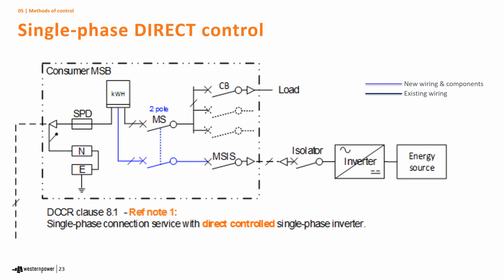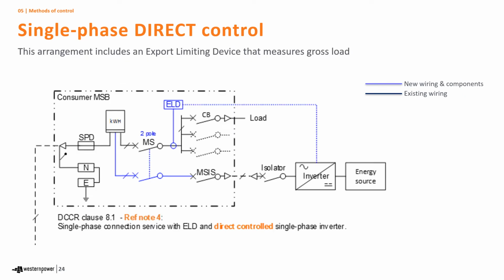Let's move on to the next example. In this example, you can see that we've added an export limiting device. This export limiting device can measure the gross load, and so it still enables you to direct control the single phase inverter with the meter directly. So you still have an additional pole on the main switch, the export limiting device communicating the load to the inverter, and then the meter directly switching the inverter on and off when required.